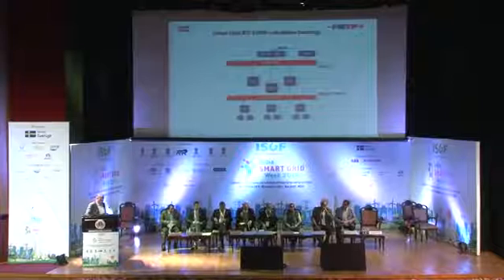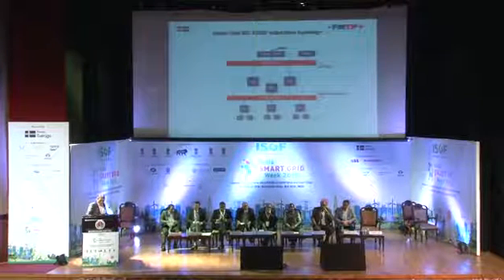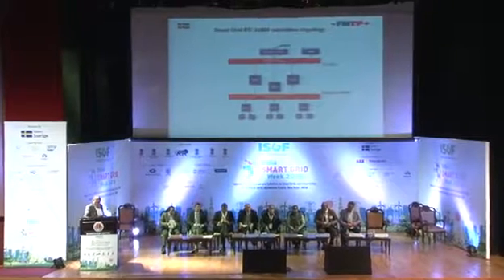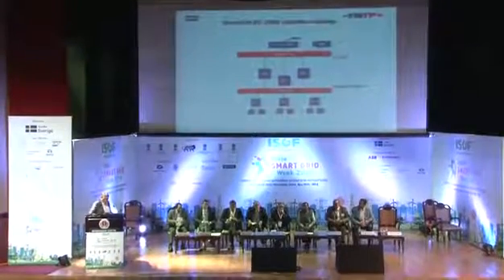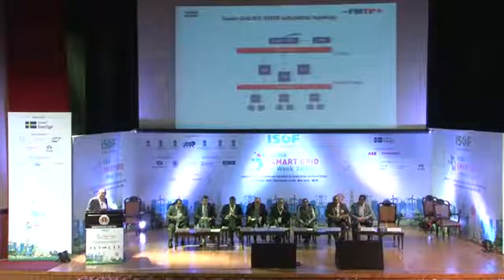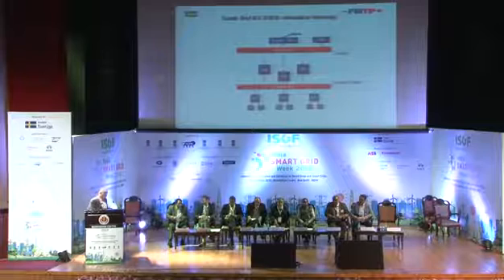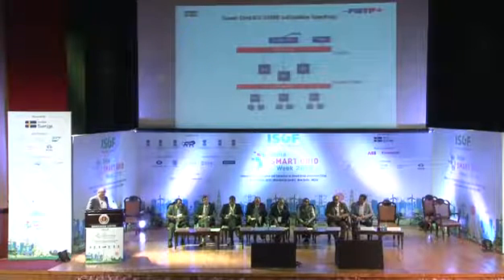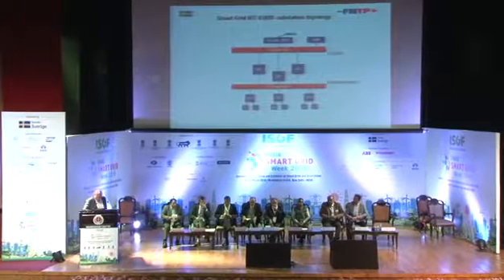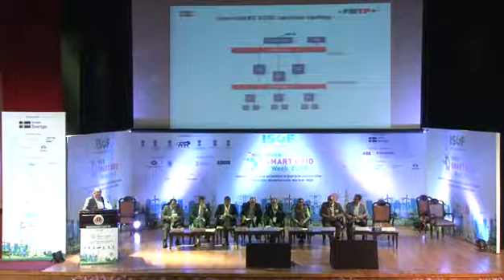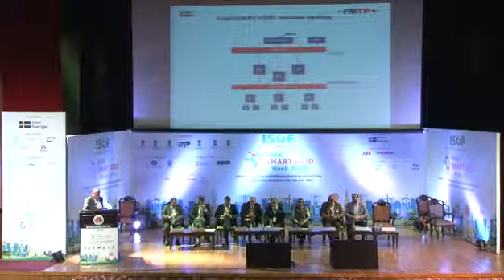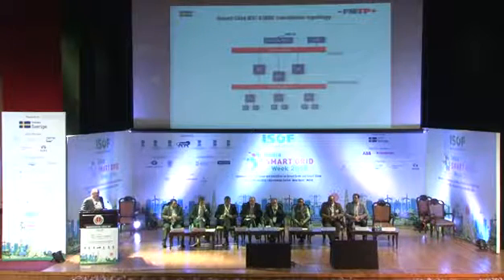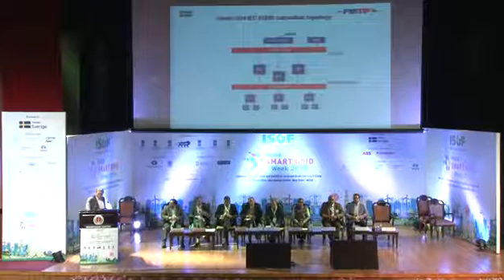This is a simplified structure of a station. We have a so-called station bus, and on the station bus we mainly have Goose communication, or some SCADA MMS also. And coming up more and more is the process bus, with merging units for standard voltage and current transformers. But nowadays we have direct digital voltage and current transformers coming up also, so we are talking about sampled values and Goose in my presentation.